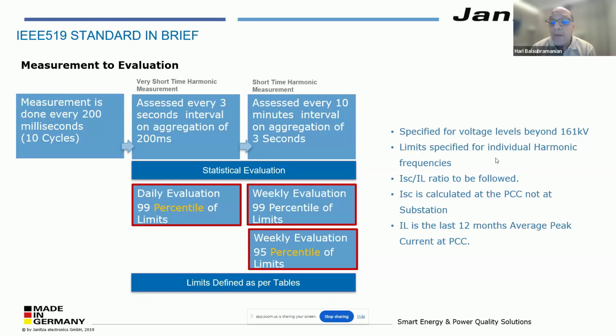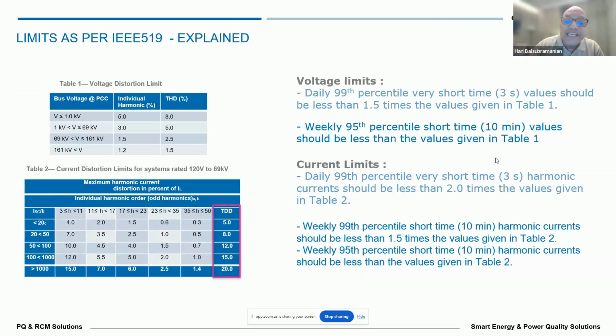So the amount of data we are handling with this standard is humongous. That means the 3 second values we collect on a daily basis per parameter. So what are all the parameters we collect? TDD, harmonic 50. So current harmonics and voltage harmonics, that is 300 values for all the three phases.